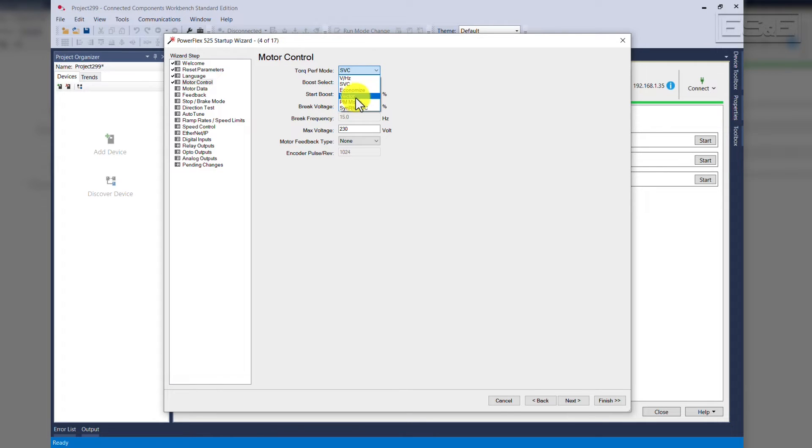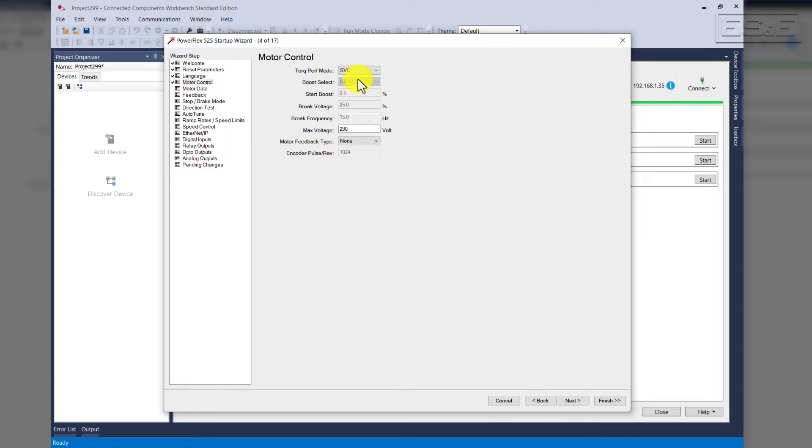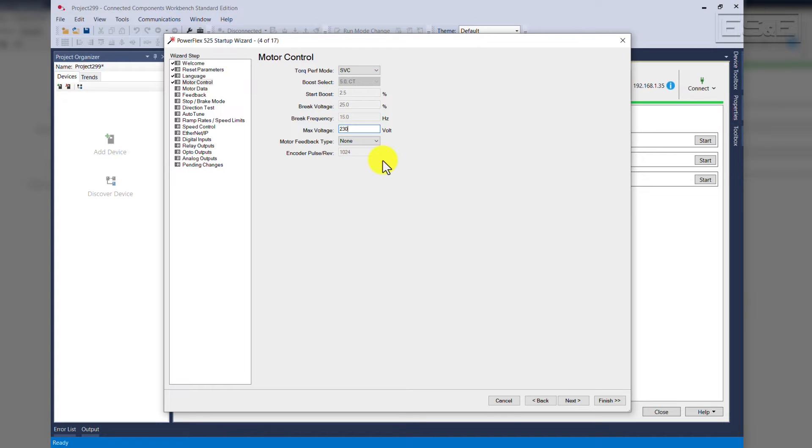vector, PM motor, etc. But for our application, we'll keep it at SVC, which is sensorless vector control. Our voltage will be 230 volts, and we do not have an encoder, so we do not have feedback for this application.